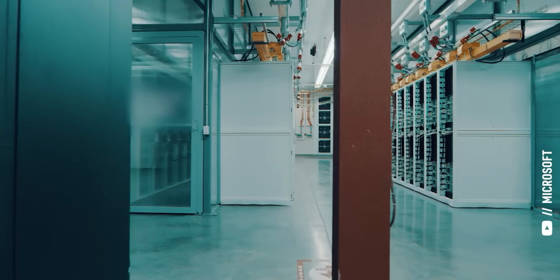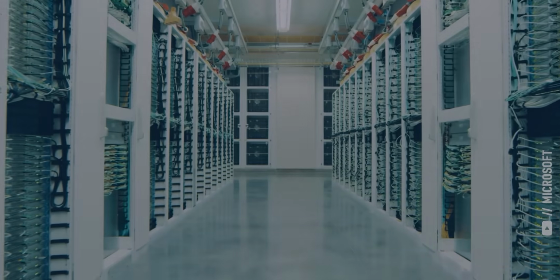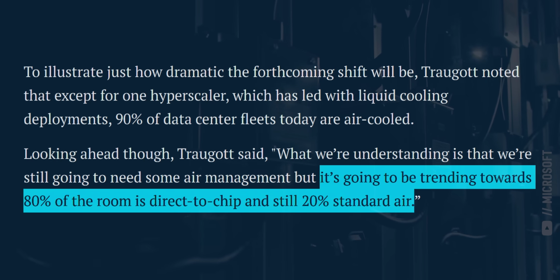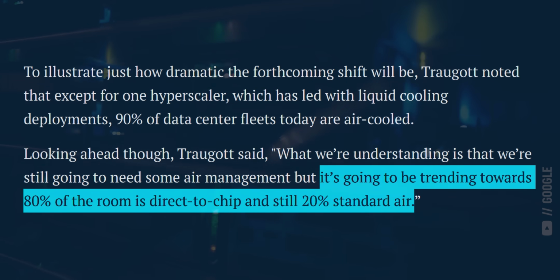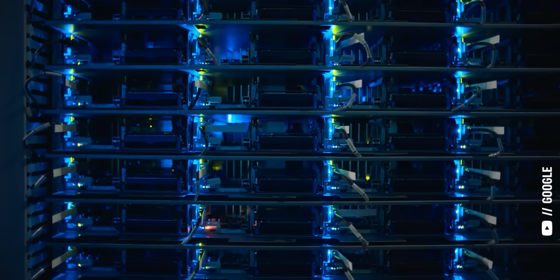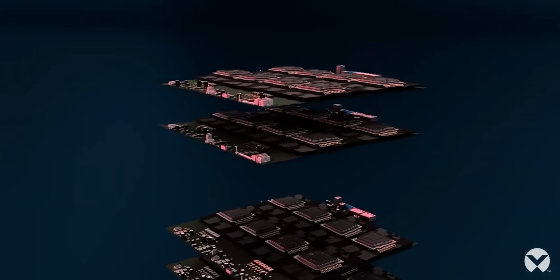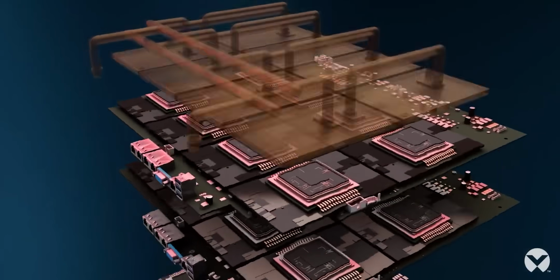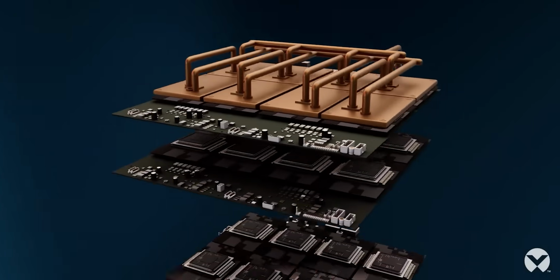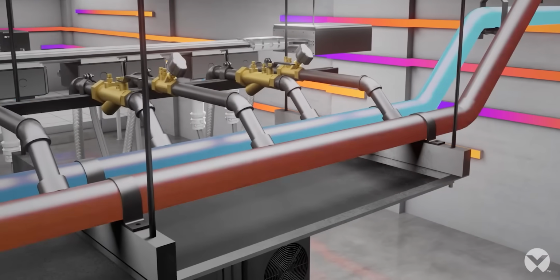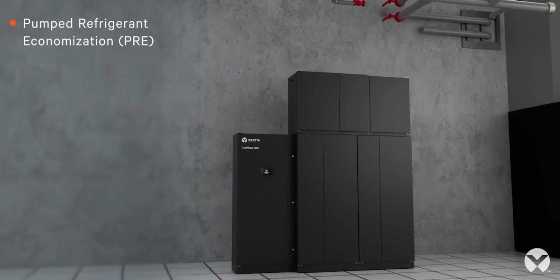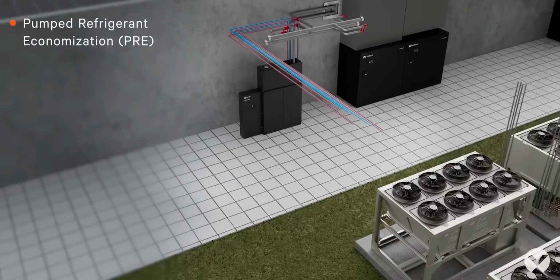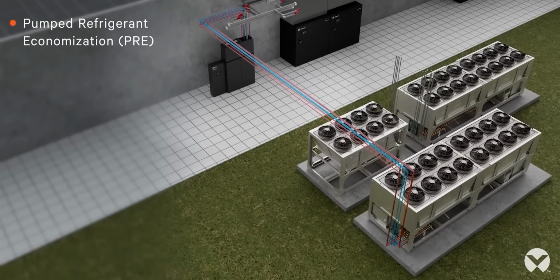90% of all server racks are air-cooled today. But industry estimates suggest that up to 80% of data center cooling will become direct-to-chip liquid cooling over time. Direct-to-chip liquid cooling is where a heat-conductive copper plate sits on top of a chip, just like a normal heatsink. But instead of being air-cooled by a fan, the plate is connected to two pipes. One pipe brings in cool water to absorb the heat from the plate, and the other pipe moves hot water away. Direct-to-chip liquid cooling is up to 3,000 times more effective than air cooling.